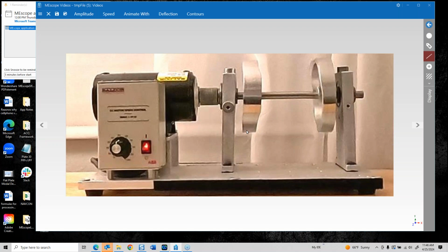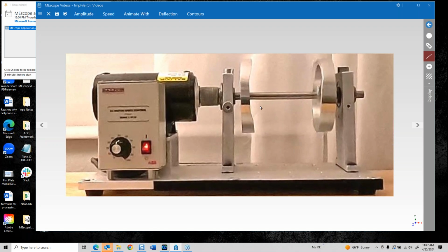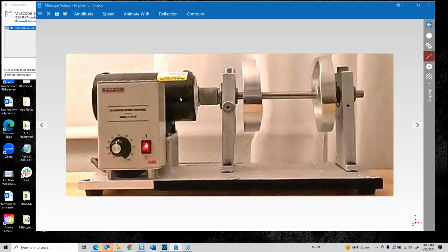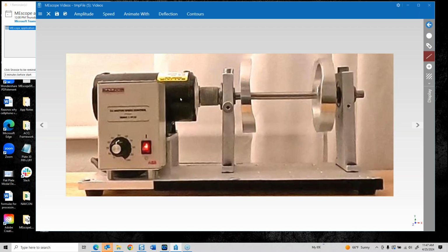It is the resonance, and you can see how they vibrate differently at 1300 RPM. And then we also have motion of the bearing blocks. If I'm really using that data to compare with last week's data or any other archival data, the ODS data, Vibrant has software for doing all those things. Anyway, I'm going to wrap this up.